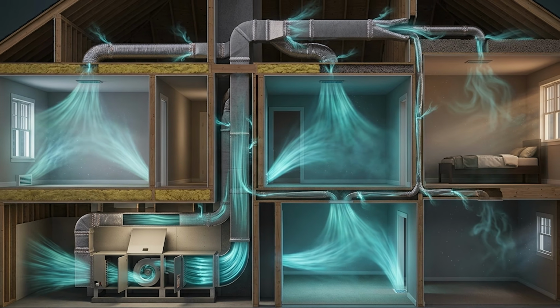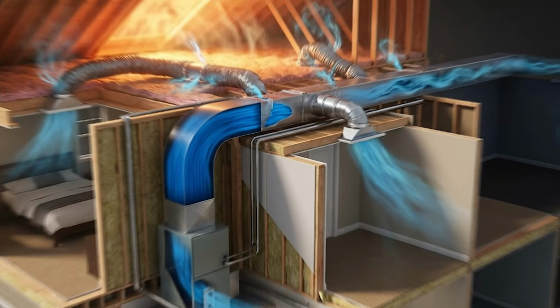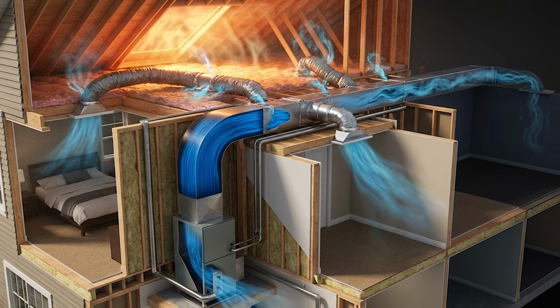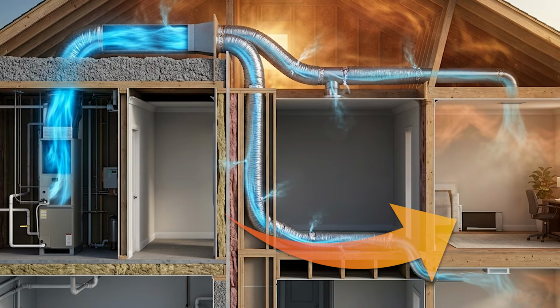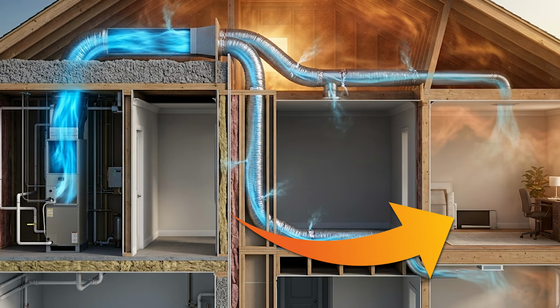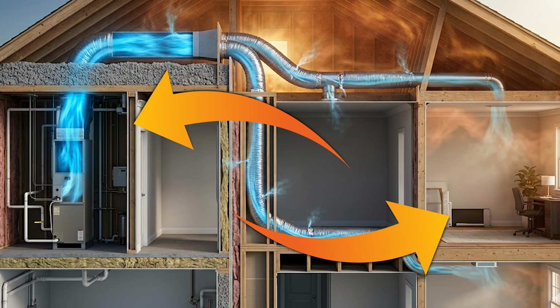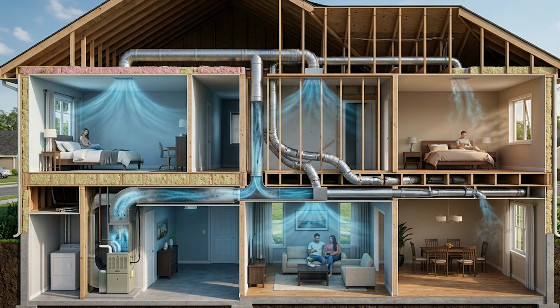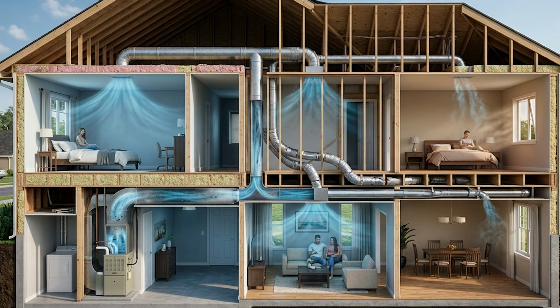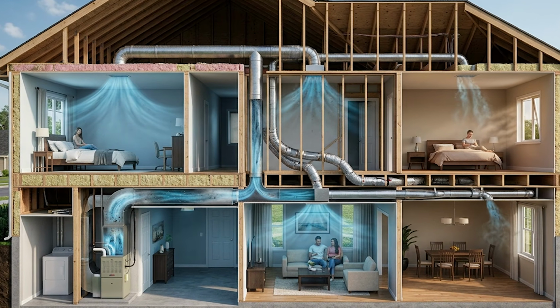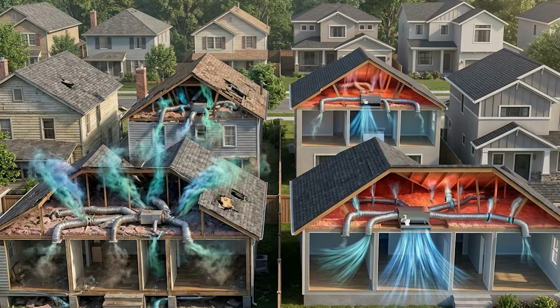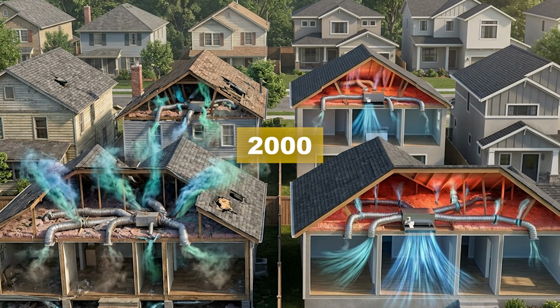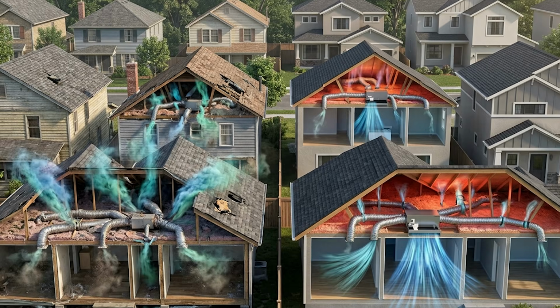And the room that suffers most is always the one farthest from the air handler, because air follows the path of least resistance. When there are leaks along the way, the pressure drops. By the time the air reaches the room at the end of the run, it has lost so much volume and pressure that what comes out of the vent is barely enough to make a difference. The rooms closest to the air handler get plenty. The room at the far end gets whatever is left. That is not bad luck, that is physics. And it is happening in almost every home built before the year 2000, and in many homes built after.